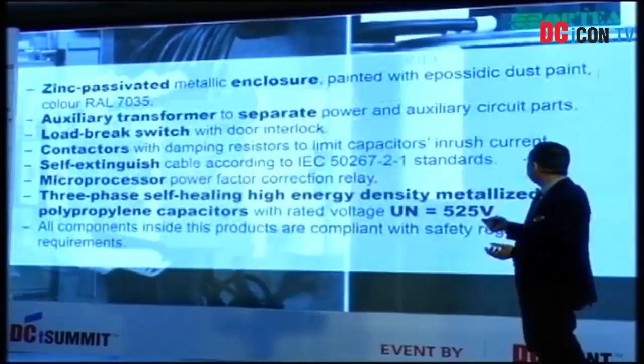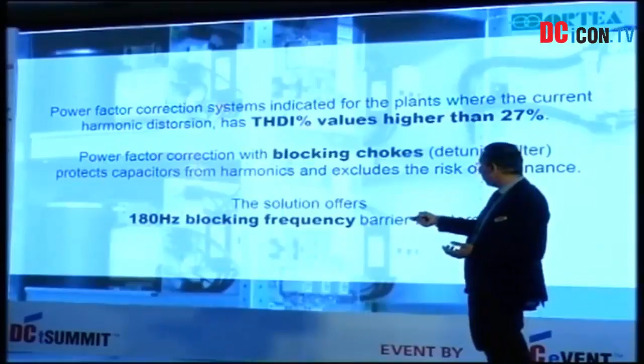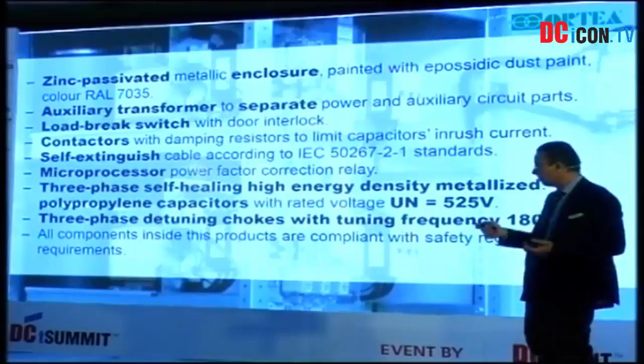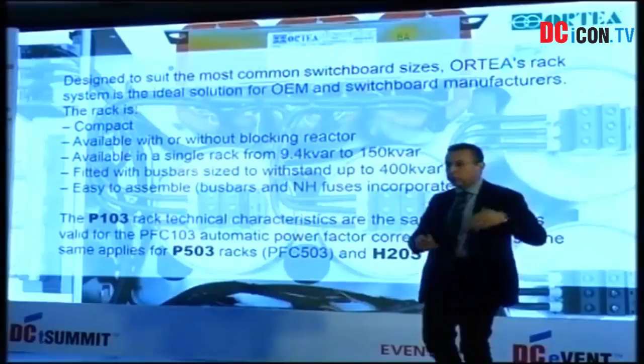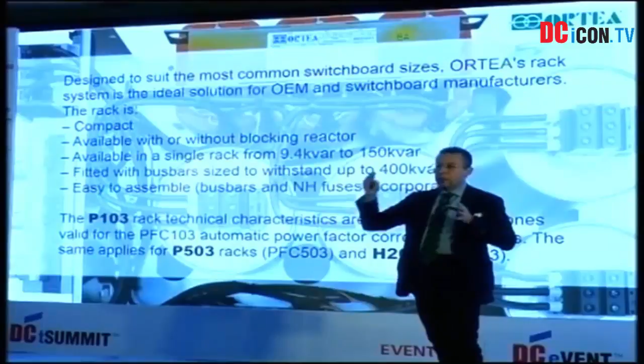So these are the most important parts of the PFC systems. So in different types. This is the version with chokes. You can see here the chokes. So these are with the 180 Hertz blocking frequency barrier, but on request also we can do differently. The same, but these are working on 525 volts till 1000 kVAr, the same configuration. These are the racks. So each unit is composed by different racks, what you call grade. So each step will be made by a different grade, starting from 12.5 to whatever we want according to the construction we need.